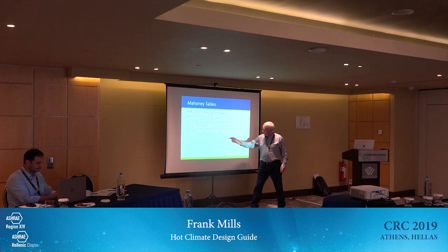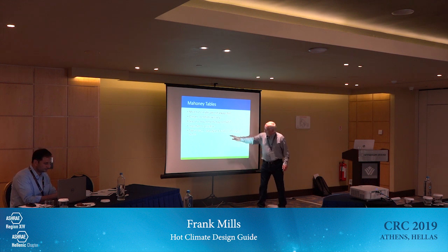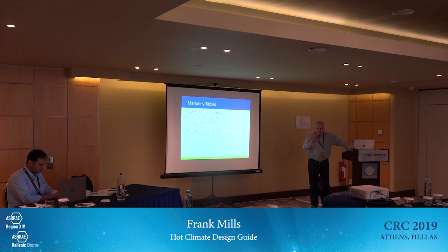You want to look at the severity and duration of climatic factors. On this particular point here, there's a paper I've got which is saying, and this is this particular writer's idea, if you are designing a building and you work out that it needs air conditioning for 9 days a year, and the other days it's all right, you wouldn't do it. You would just say to the client, it's not worth doing. You don't want to pay for all this air conditioning equipment if you're going to run it for 9 days. So for 9 days, you're going to be a bit too hot, get some complaints, but that's it.